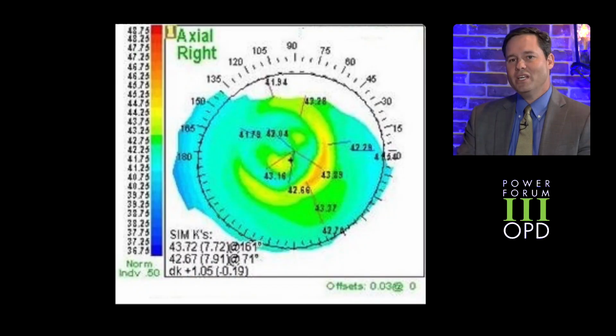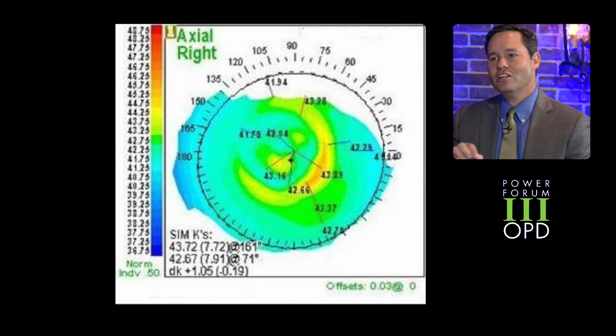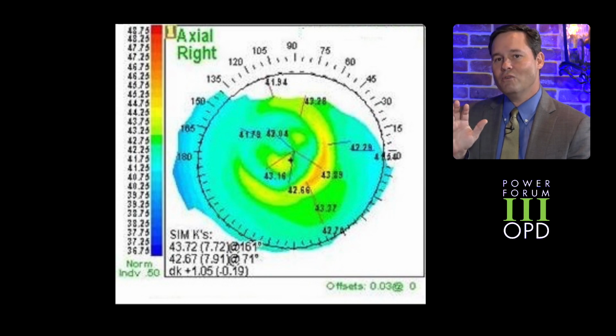We had a beautiful corneal map show up, and we'd already gotten the biometry on the patient. They were going to get scheduled for surgery, and it had a big, almost like a C, almost a full annulus right there at about 3 millimeters. That was a perfect Goldmann. The fact that that machine could pick that up was amazing right then and there. When I looked at what the measurements were going to be, I had the patient come back, and found out that we were going to have been a whole diopter off on our targeting.